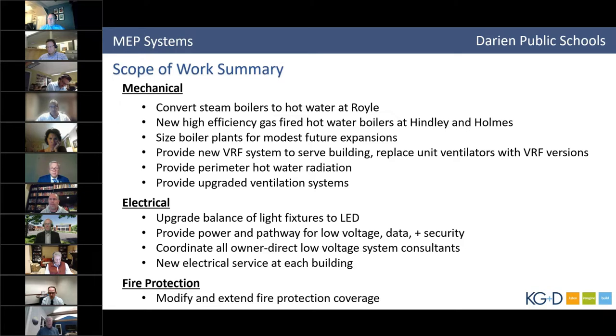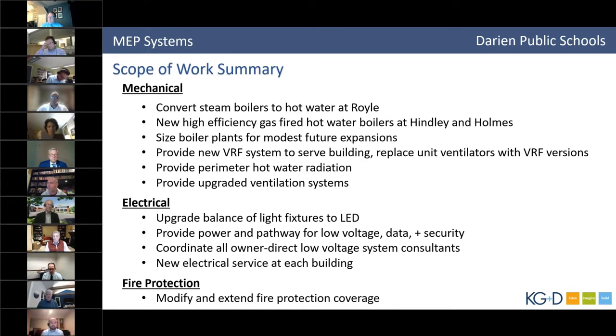Also, in terms of tonnage - to set parameters, you have about 25 classrooms in each building. Is that correct? 24, 24, and 22 - did I understand that correctly? Yes, that's correct. If each classroom is 800 to 900 square feet, are you talking 3 to 4 tons? I assume with large windows and probably no new insulation, 3 to 4 tons of AC per room? Each about 4 to 5 tons. Even better, I think that's great.